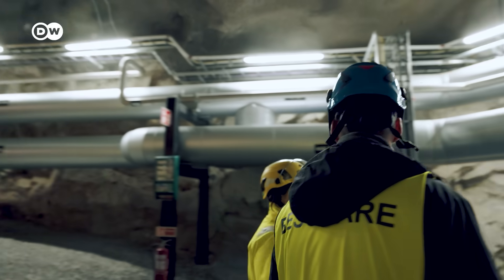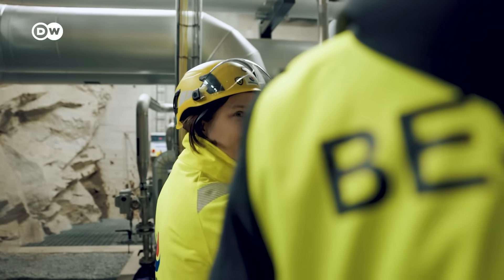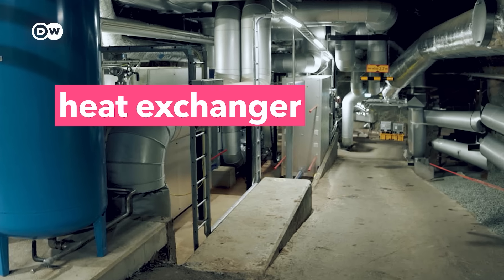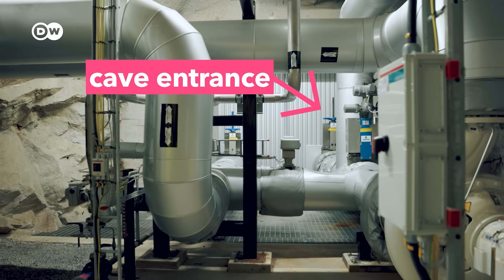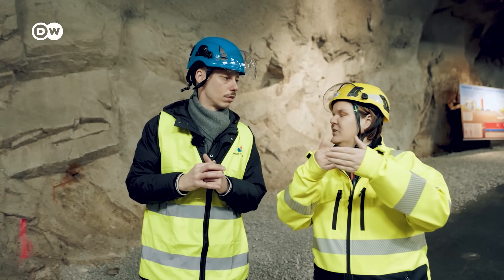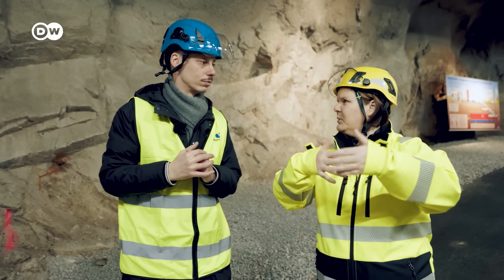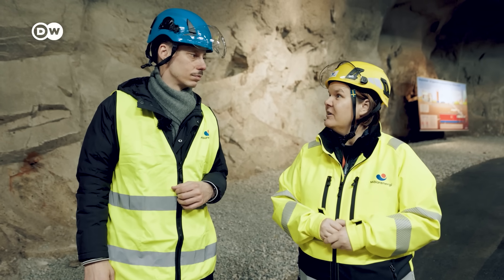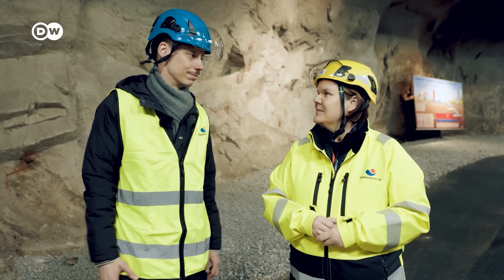What's all the noise? These are the pumps working now — taking the warm water from the top of the cavern and sending it to the heat exchanger. This transfers the heat from the water in the caves to the water running through the district heating network. Unfortunately, this is as close as we can get to the caves, because they're sealed. On the other side of that steel you have concrete — a concrete plug. Because on the other side there's 102,000 cubic meters of 95-degree hot water. So if it's not plugged properly, we'll be cooking.